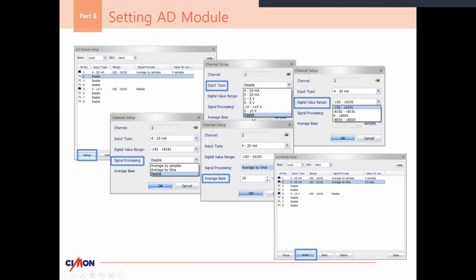It looks like they're going to disable it here, but this is just showing the different options available, like 4 to 20 or 0 to 20. I recommend staying away from 0, because it's really hard to troubleshoot: if it's off, it reads 0, and if it's not working, it also reads 0, so you can't distinguish the two. If you choose 4 to 20, when it's off it'll read 0, so you know it's off. When it's on, it should always be a bare minimum of 4. If it's on and reads 0, you know something's wrong, since 4 is the minimum.